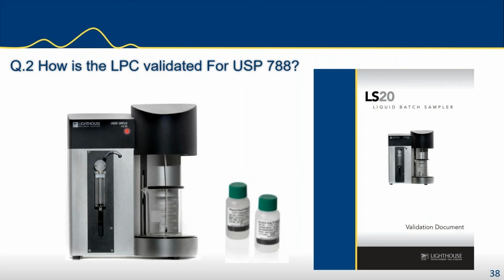As long as you meet that 10% requirement for count accuracy. So if you have this concentration, say 3,000 particles per milliliter, you should fall between 2,700 and 3,300 at the 15 micron size. That will enable you to verify that you've passed the test.